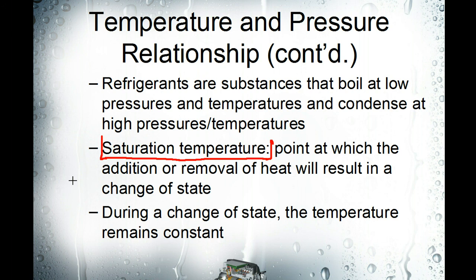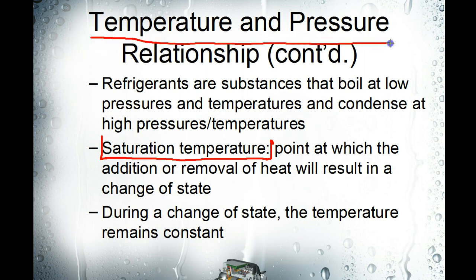Or if we add one extra degree of heat to that container, it's going to change the state of the liquid to a vapor. Saturation temperature is the point at which any heat either added or removed will result in a change of state. All of the pressure-temperature charts we look at, we're talking about the refrigerants at the saturation temperature — that is the point where heat added or removed will change it from liquid to vapor and vice versa.